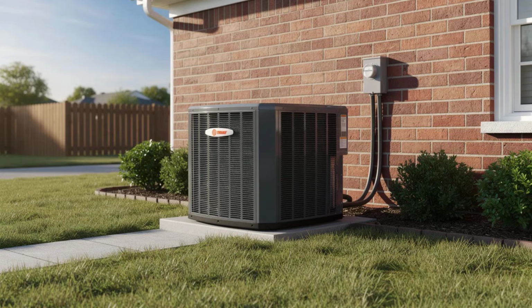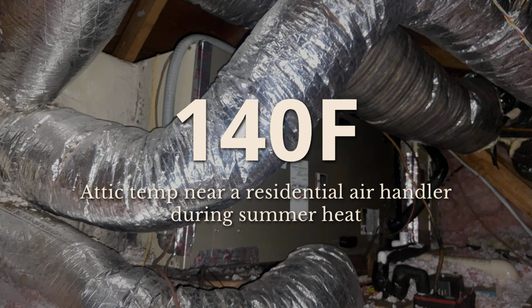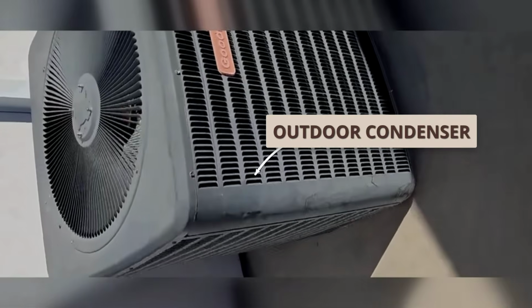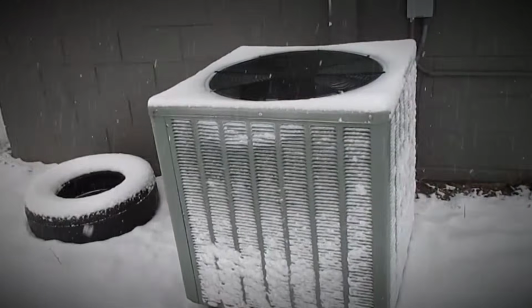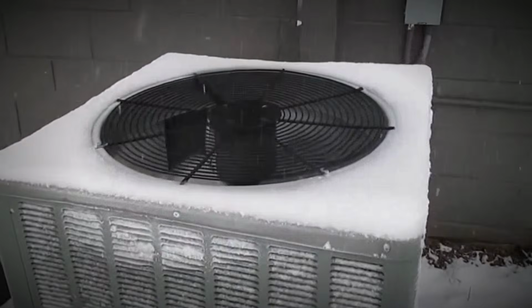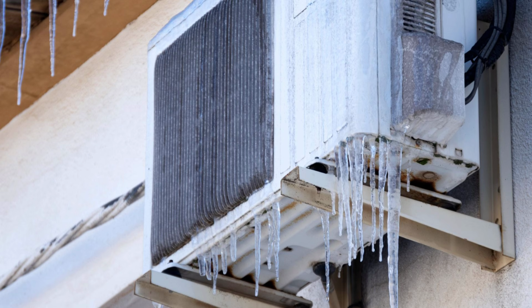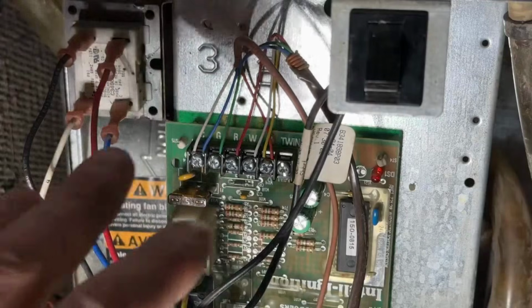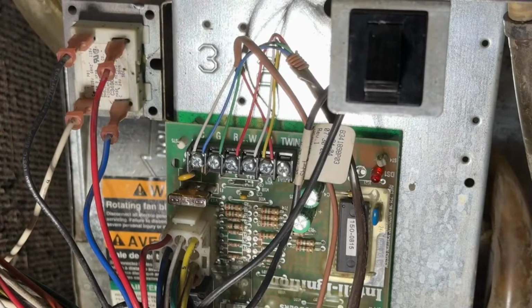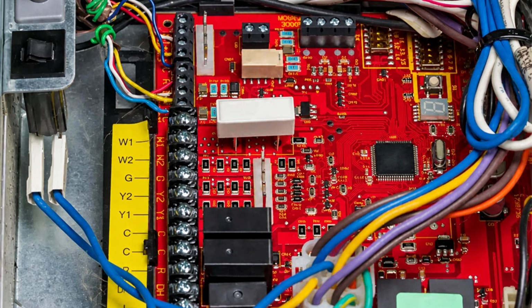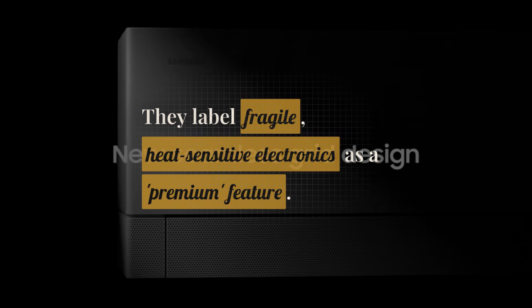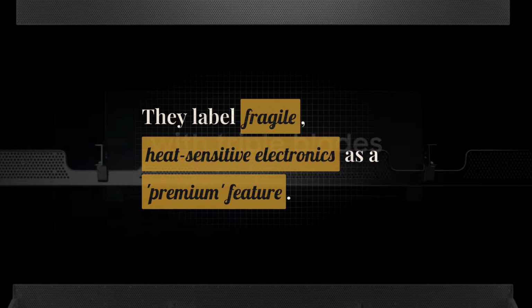Consider where these components live. A residential air handler sits in an attic that routinely reaches 140 degrees in the summer months. The outdoor condenser unit sits exposed to direct sunlight, driving rain, ice storms, and sub-zero wind chill. These are among the single harshest operating environments anywhere in your house. And manufacturers are mounting delicate silicon circuit boards, heat-sensitive electrolytic capacitors, and thin ribbon cable connections directly inside these machines and calling it a premium feature.